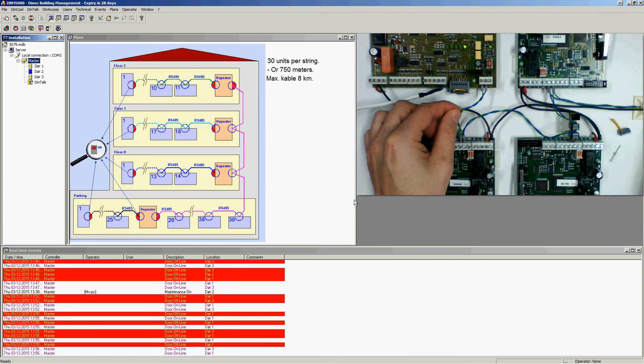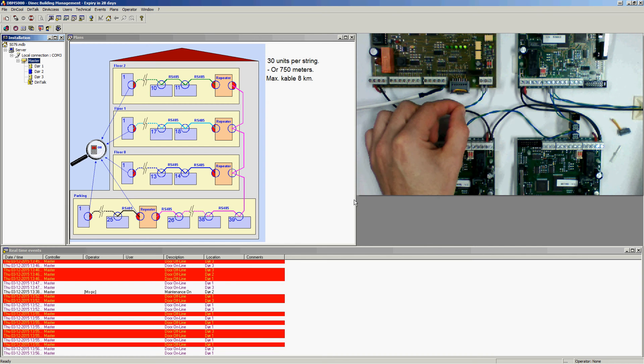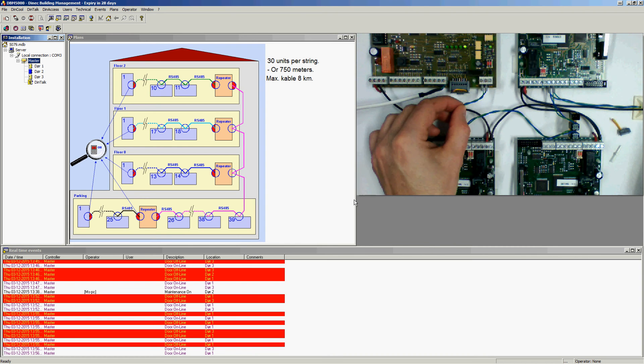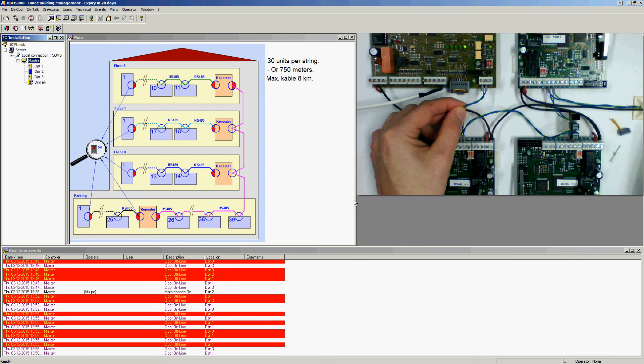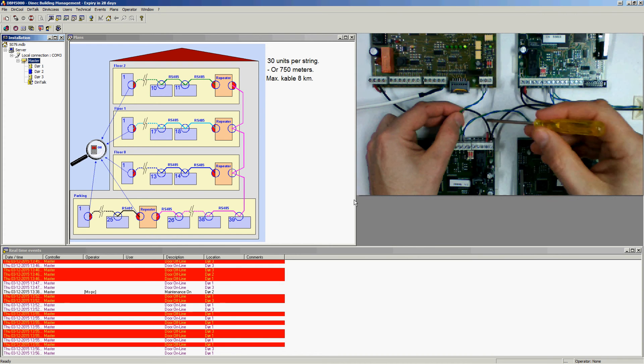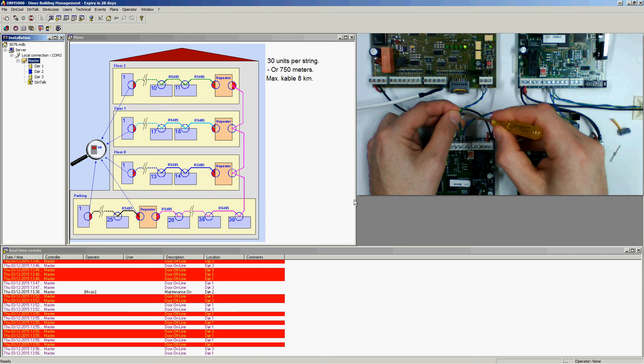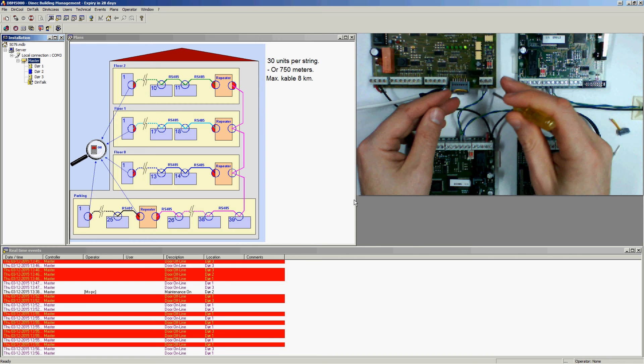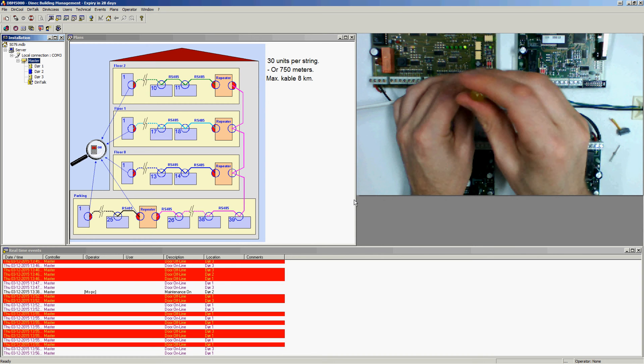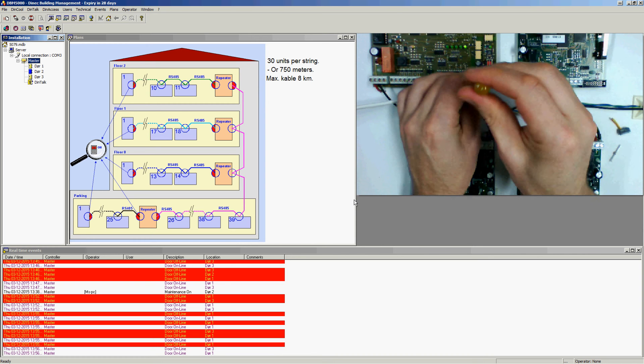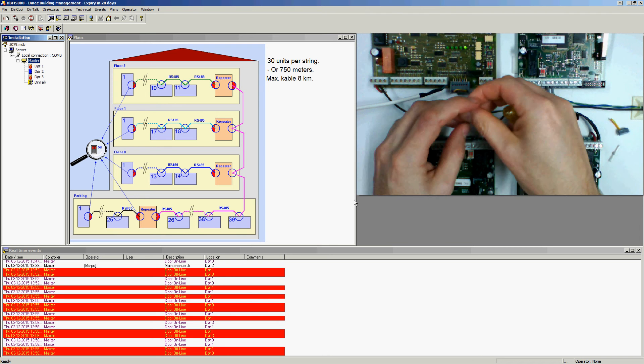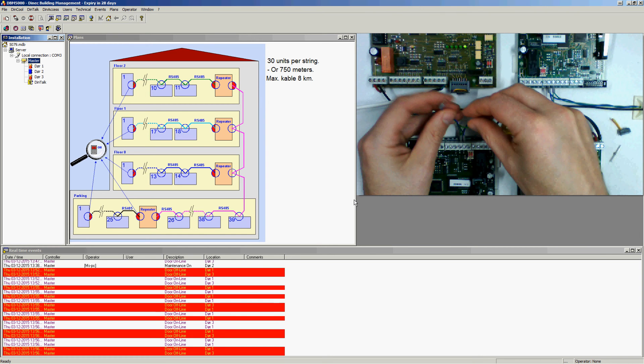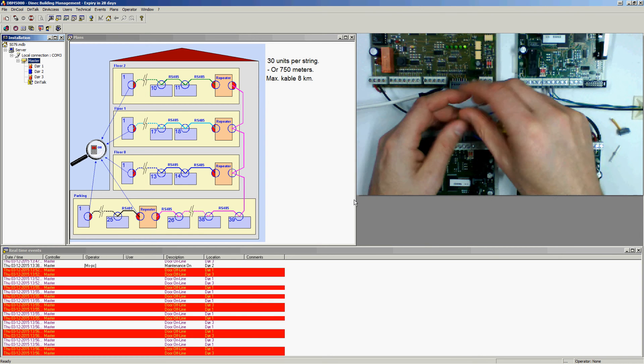You have to make sure that the cable you're using is of course shielded. And if it is twisted, the rule says you have to have one twist every 1.5 centimeters. Many people, when they isolate the bus cable, may have about 15 centimeters or so for each unit — just connected like this.